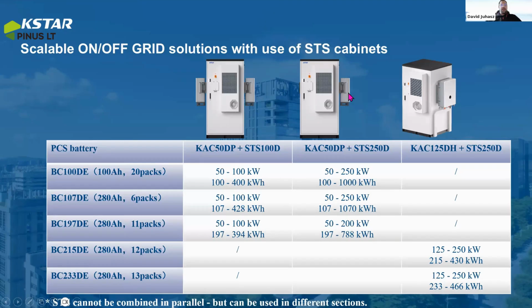And in case we are using the old one, KAC50DP, we can also use it in off-grid solutions, but in that case we need to add the system STS devices, which are standalone cabinets with a switchover device included and transformer inside included. And this also makes possible the switchover in between 10 milliseconds to prevent the blackout.